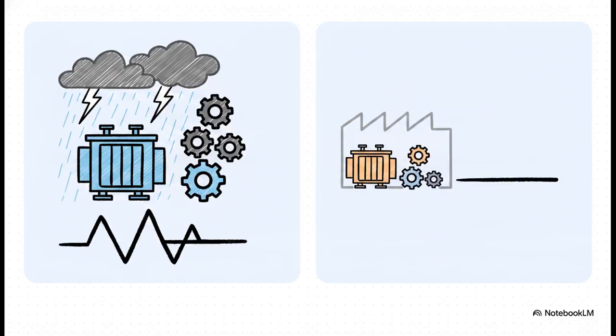And right off the bat, here's an awesome rule of thumb for you out in the field. Generally speaking, oil-immersed transformers commonly use a 7-step tap range, whereas your dry-type units commonly use just 5 steps. Why the difference? Well, oil-immersed units are usually out handling much wider incoming voltage swings on longer feeders. Dry-type units are usually tucked away indoors, much closer to the source where the voltage is inherently more stable.